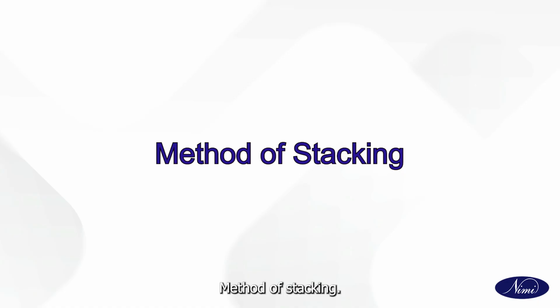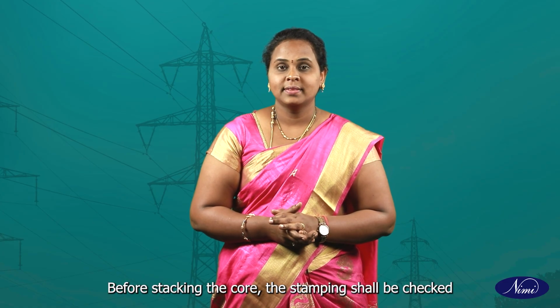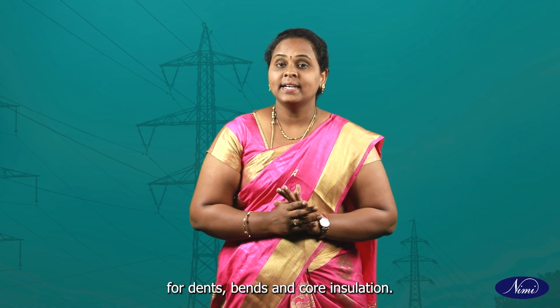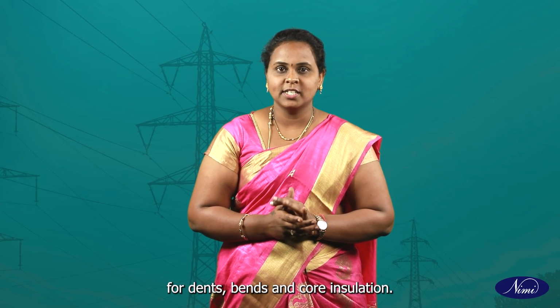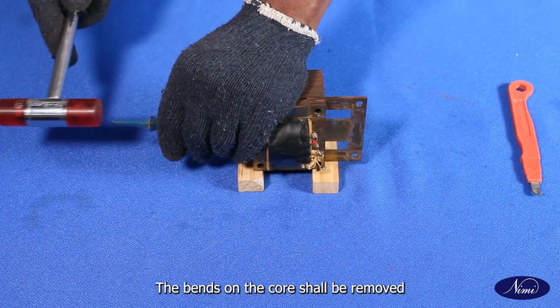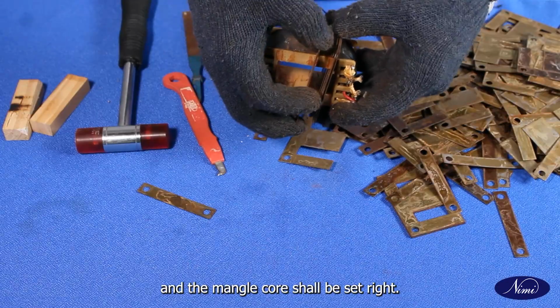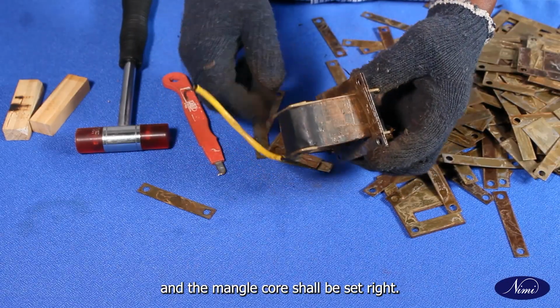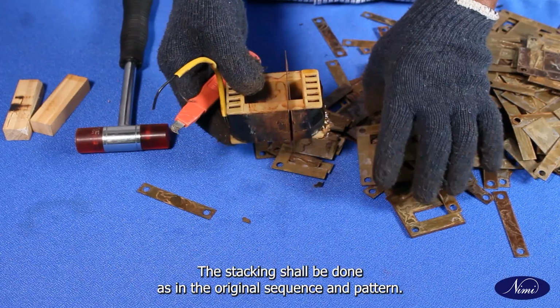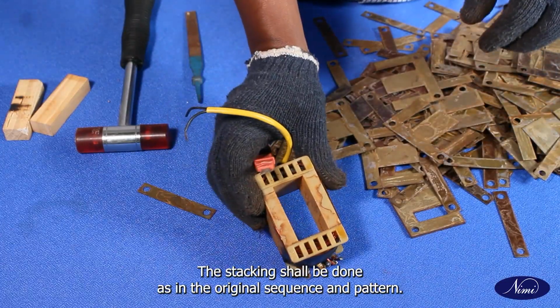Method of stacking. Before stacking the core, the stamping shall be checked for dents, bends and core insulation. The bends on the core shall be removed and the mangled core shall be set right. The stacking shall be done as in the original sequence and pattern.